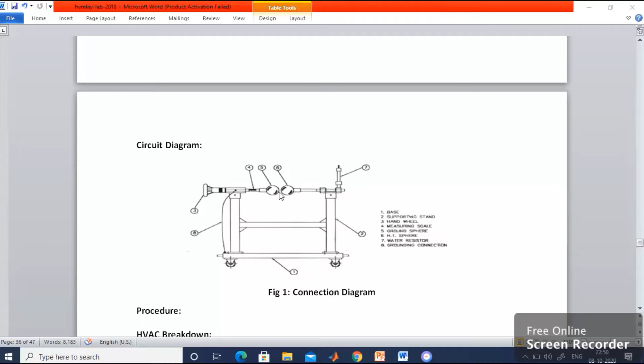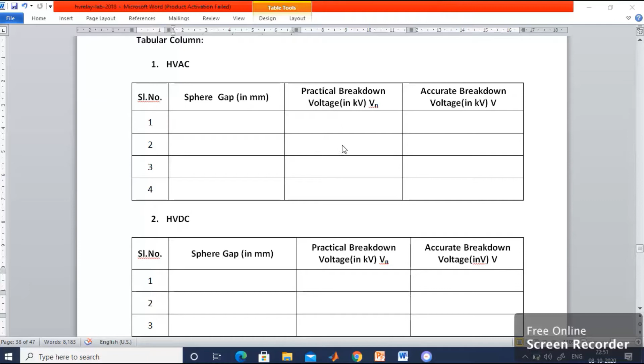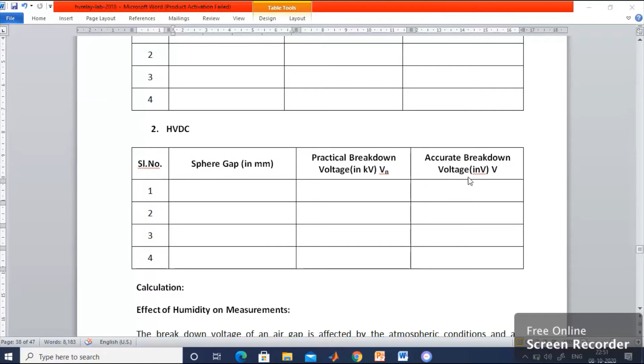This is your tabular column. You need to maintain the sphere gap distance at 5 mm, 10 mm, 15 mm, 20 mm, and so on. Then you measure the practical breakdown voltage and calculate the accurate breakdown voltage using a standard formula, as already explained. Similarly, when applying HVDC, you maintain the sphere gap at 5 mm, 10 mm, 15 mm, and 20 mm, measuring the practical breakdown voltage in kV each time, from which you calculate the accurate value of breakdown voltage. So this is what you are supposed to do.